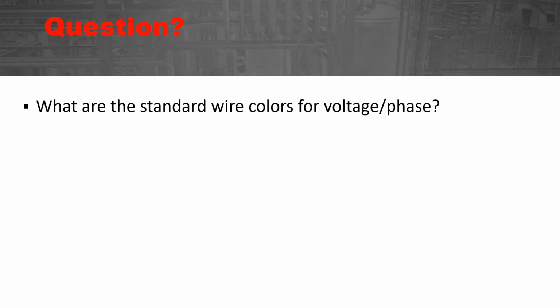And sometimes I'll hear someone say, well, we never have those two in the same enclosure. And I go, wait a minute. Do you have 480 volt in and then you hit a transformer and then out of the transformer you have 208 volt three phase coming out? And yeah, they have that. Well, you have 480 and 208 in the same enclosure in a transformer.